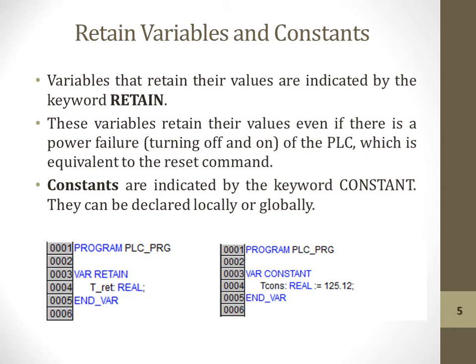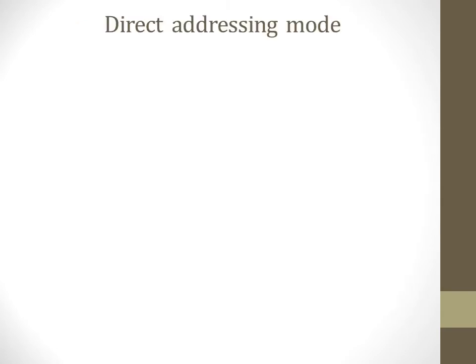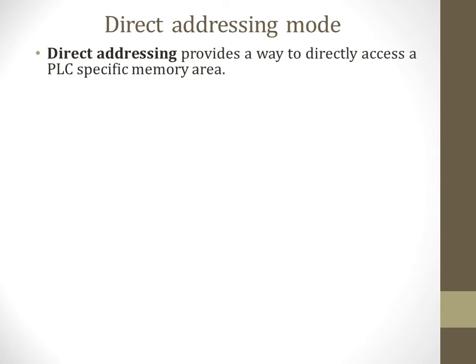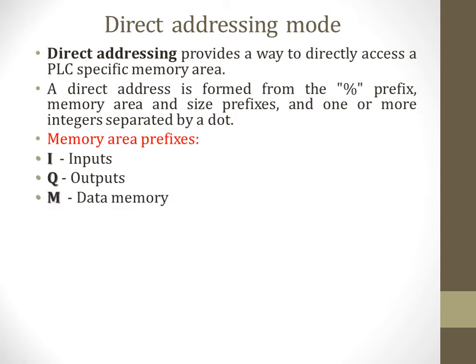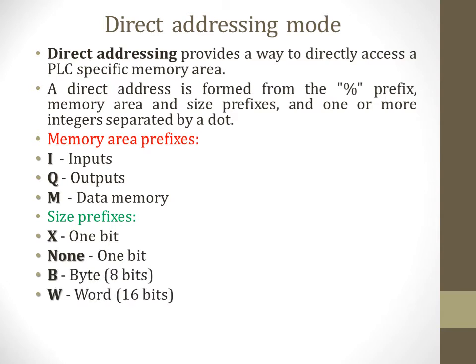This is an example of how to declare a retain variable, and this is an example of constant variables used in programs. The next topic is direct addressing mode. Direct addressing provides a way to directly access a PLC-specific memory area. A direct address is formed from a prefix, memory area, size prefix, and one or more integers separated by dots. Memory area prefixes are: I for inputs, Q for outputs, M for data memory.